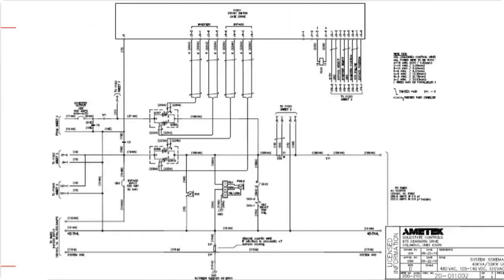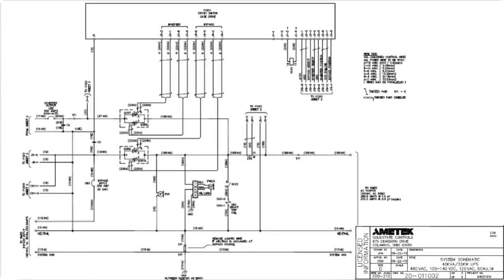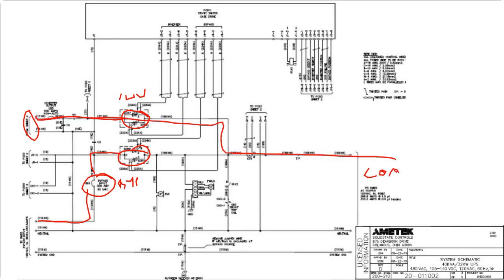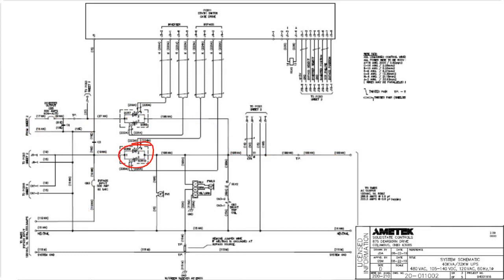And then this drawing is the static switch. It tells you which sheet it comes from, sheet 2. Obviously, this cable here is the bypass input because we have our bypass input breaker here. Therefore I know that this is the bypass static switch, and I know that this is the inverter static switch. So in normal operation, power flows down out here and out to our load circuits. Only if the inverter fails or something happens does this turn on and we have bypass flowing in out to our load directly. Okay.